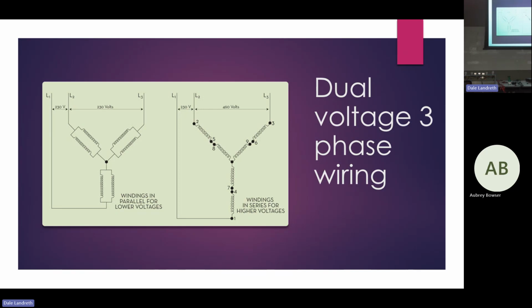What happens when we put the voltage through these coils? What does the voltage do to those coils? It's going to divide, right? So over here, in parallel, what's it going to do? It's going to stay the same. So you see what we're saying? Here, they're in series; here, they're parallel. In parallel, it's 230 volt; in series, it's 460 volt. So each wire basically gets half the voltage, right? We're doing the same thing, just configured differently depending on whatever voltage is supplied to the motor.